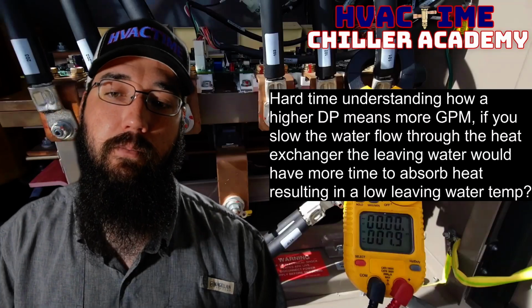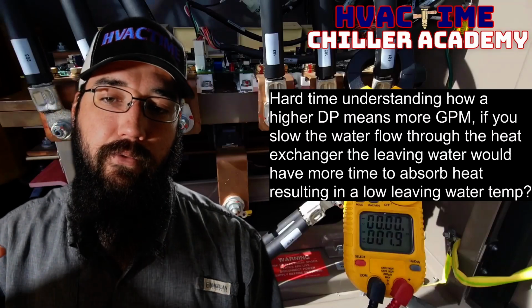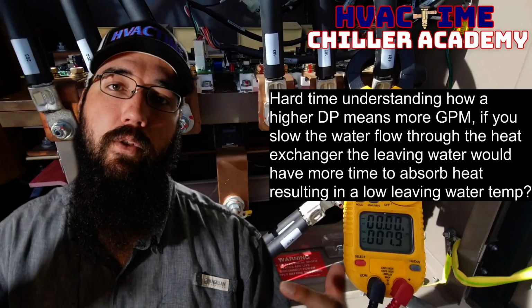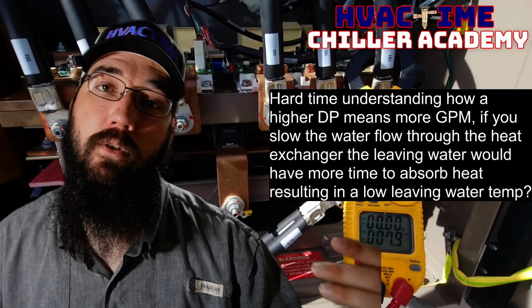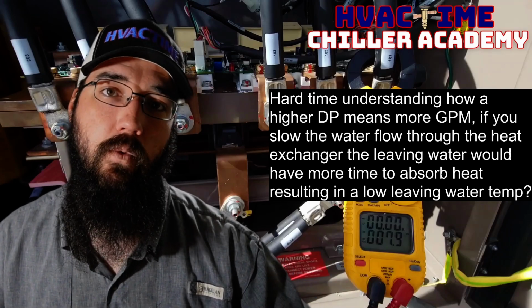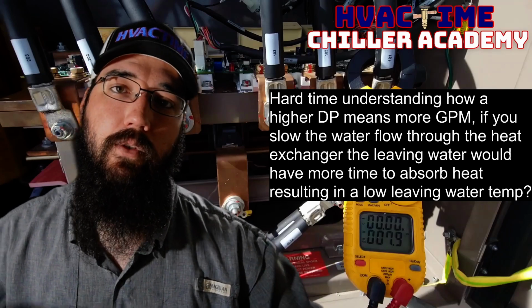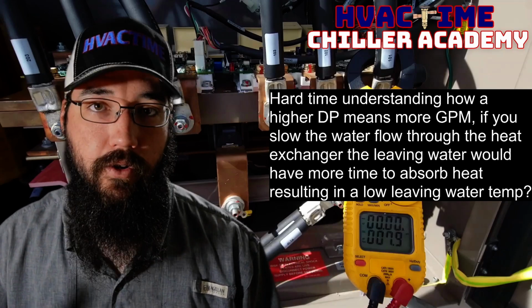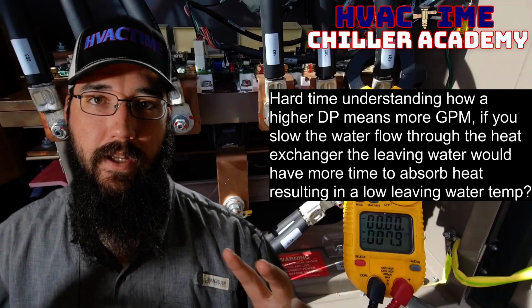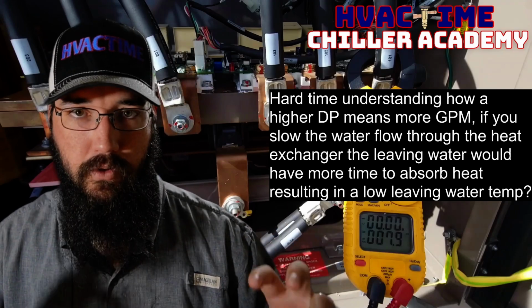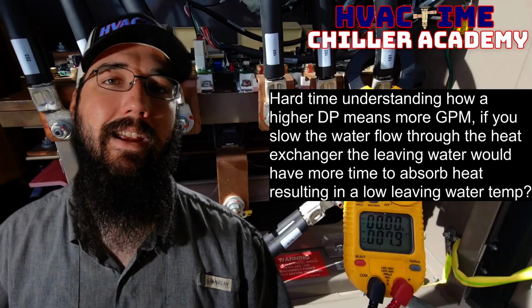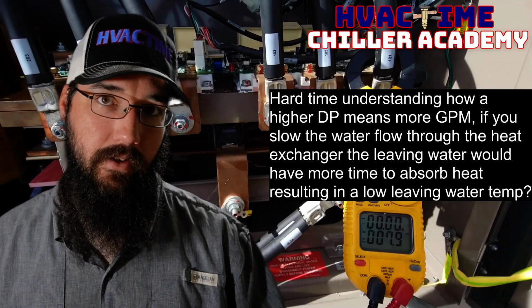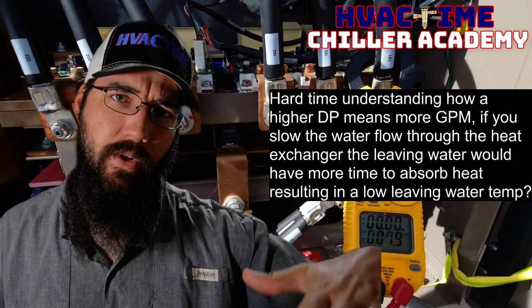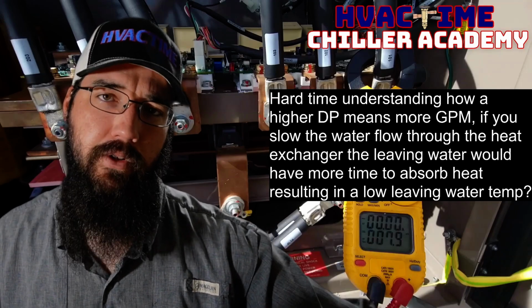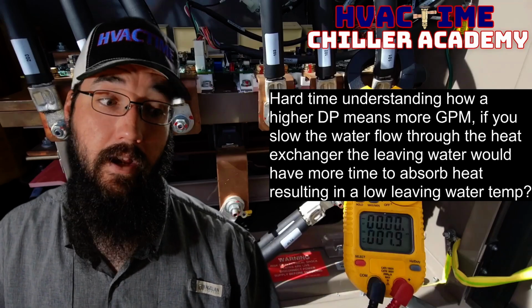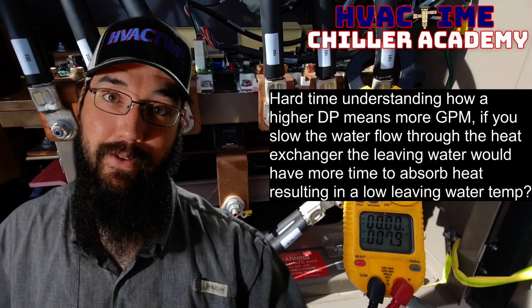So to your point, yes, if we are lowering GPM, we will make leaving water set point, or we will get colder leaving water easier. And if we're raising GPM, it will be harder to achieve that. And the goal is to hit the correct, call it sweet spot, if you will, the design point in the middle there. Because that is a symptom that we can have. We can, in some cases, force so much flow if a plant's that badly designed. And like I've come across them.